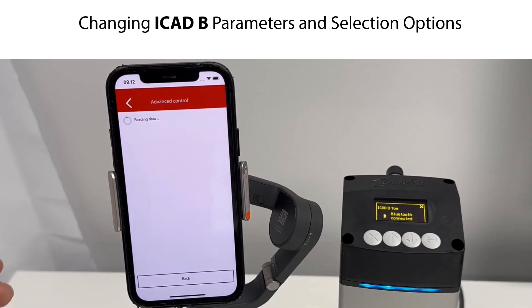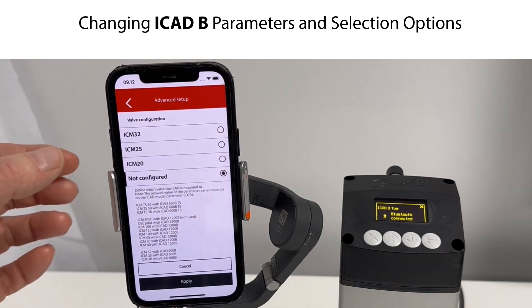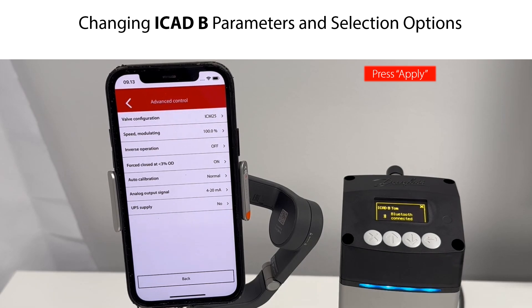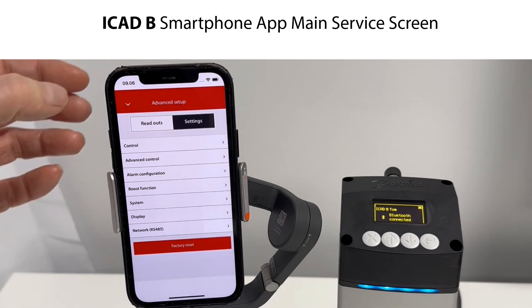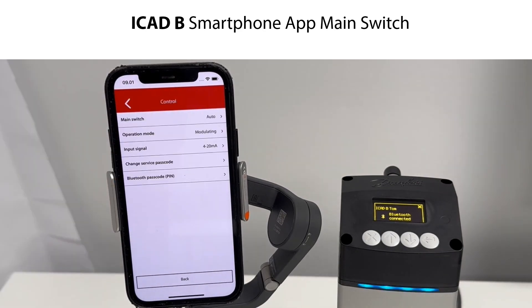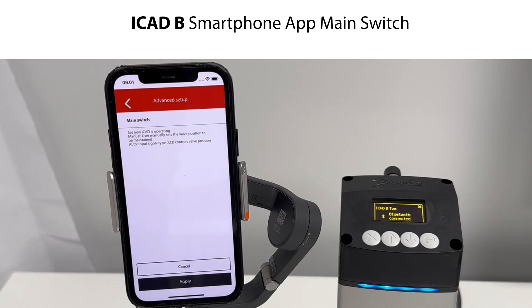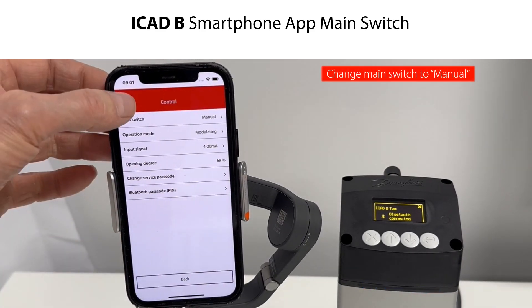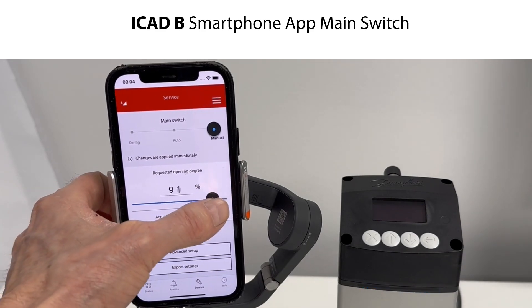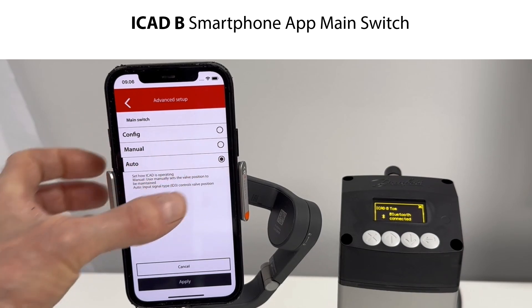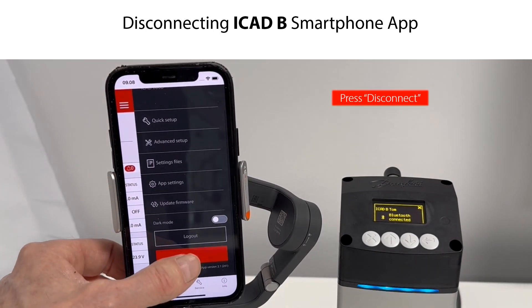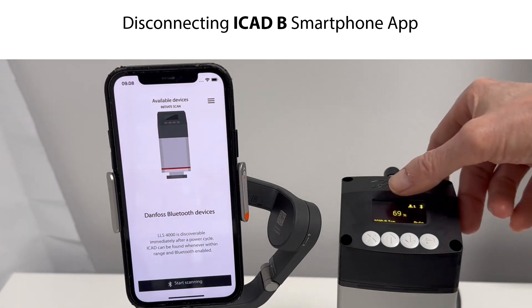You do changes to the ICAD-B parameters and selection options by simply pressing the needed parameter and selecting between the given options. Remember to press Apply after each change. Once you have completed the changes, press the arrow in the upper left corner to return to the setting menus. You can also manually change the valve opening degree by changing the main switch from Auto to Manual. Once done, change the main switch back to Auto. When setup is complete, press the menu access icon and press Disconnect — the ICAD-B will now operate the valve according to the configured settings.